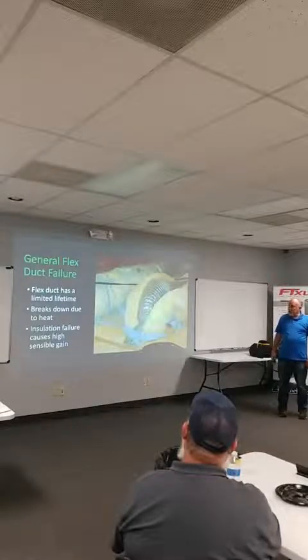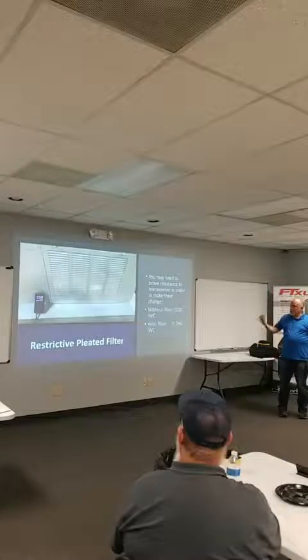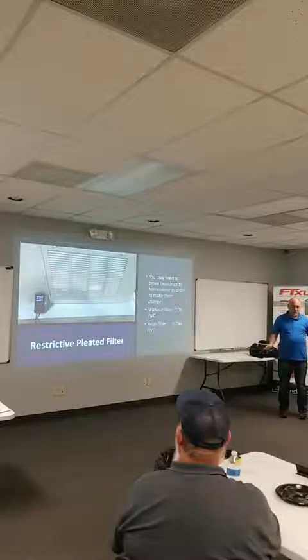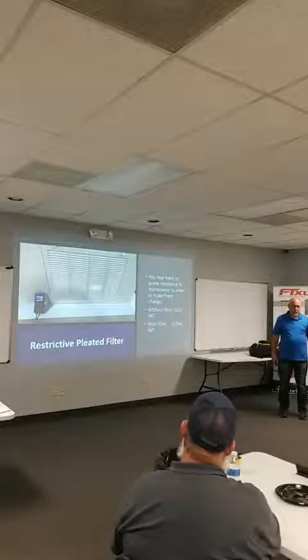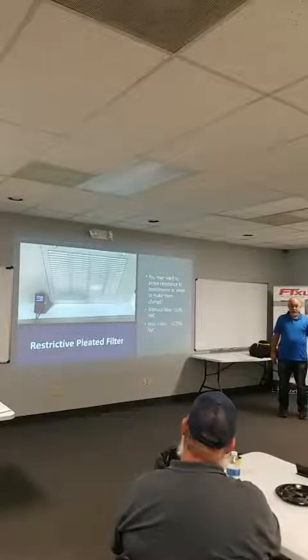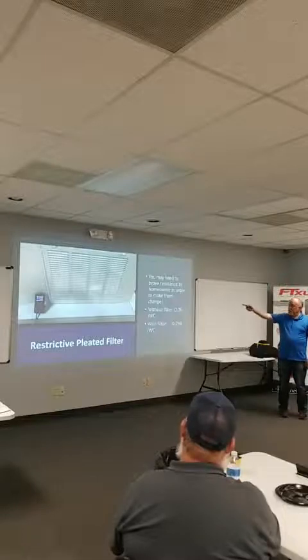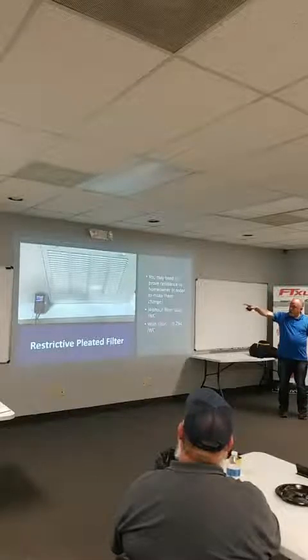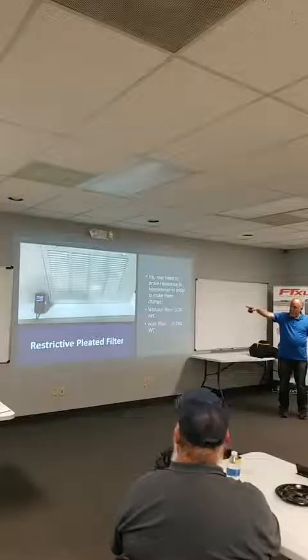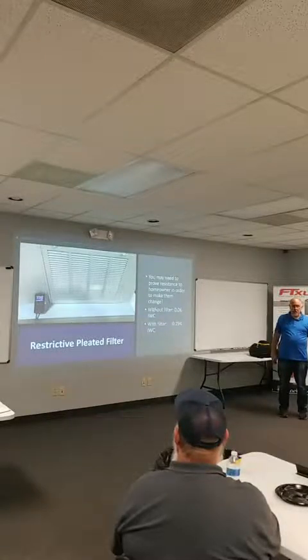Insulation breakdown, limited life. Restricted pleated filters, this is another one that we see a lot, especially with COVID right now. Everybody's going out and buying a 3M, nothing gets through this filter, including air, right? You may as well leave the plastic on because it's about that restrictive. This is one in my shop, I just put a 3M filter in there, and it was 0.29 inches of static pressure drop across the filter.